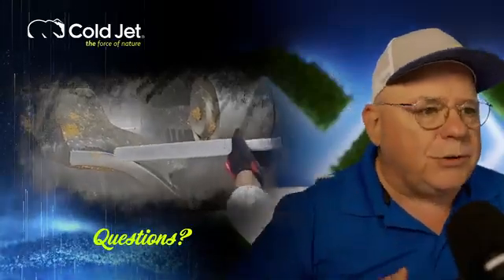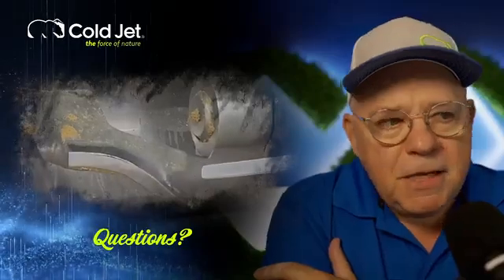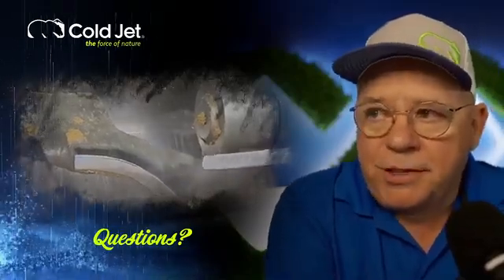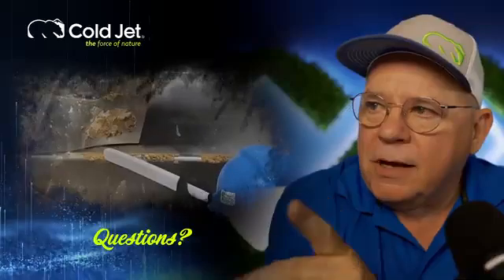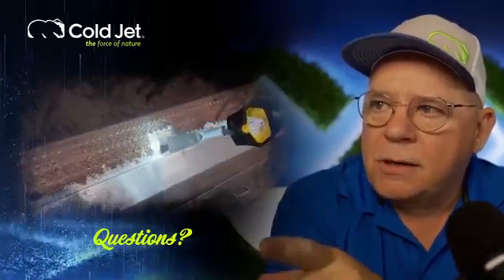So this person wants to know if we can run it in a class 1, div 1 explosion area, so like in a flour or sugar plant. Well, there is a motor in the machine, so we have a spark, okay? Now, you could park it outside, and we do have a pneumatically driven motor, okay? But still, there is static in the line. So when you send pellets through a polyfoam hose, you're stripping electrons, so you're making static. So you have to know a lot about grounding and stuff. But we do have people that do it.